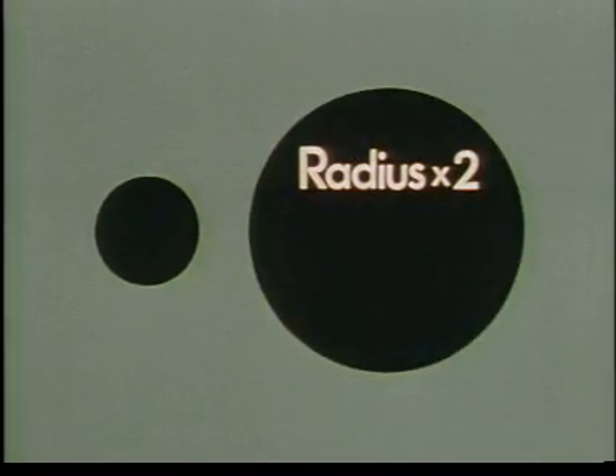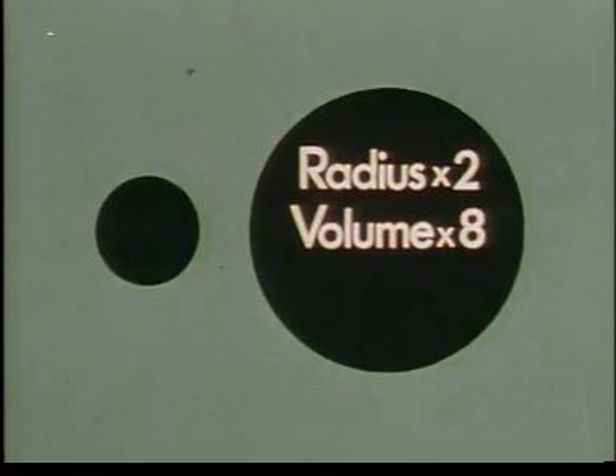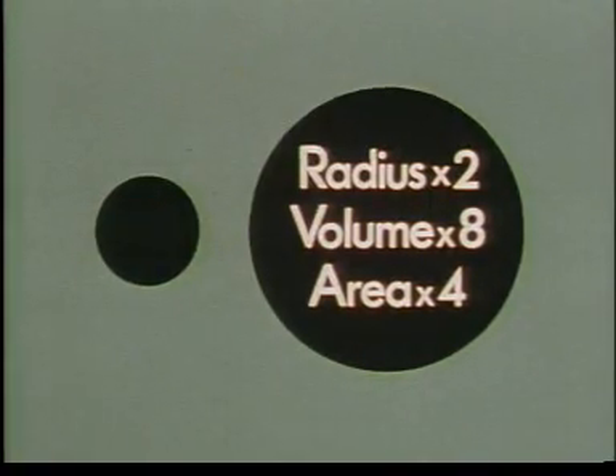The buoyancy of a globule of oil in water depends on the volume of the globule, but the speed of rising depends not only on the difference in specific gravity of the two liquids, but on the friction on the surface of the globule as it moves through the water. With a minute droplet of oil, the skin friction may be sufficient to prevent it rising at all. But a globule of twice the radius will have 8 times the volume, but only 4 times the surface area. It will therefore have a far greater tendency to rise.